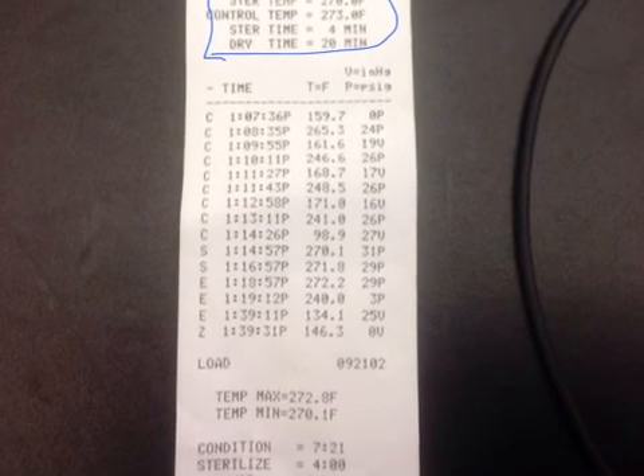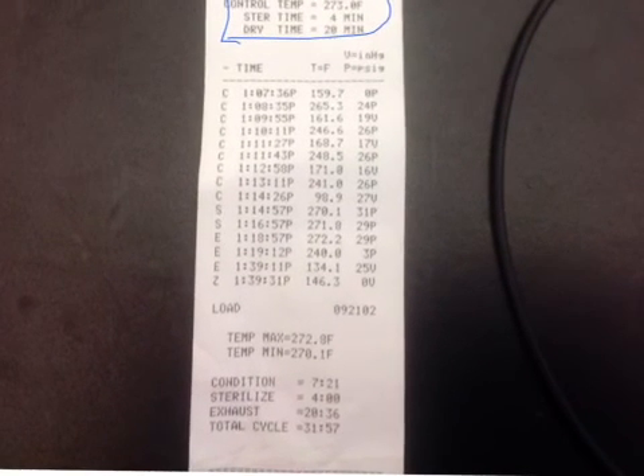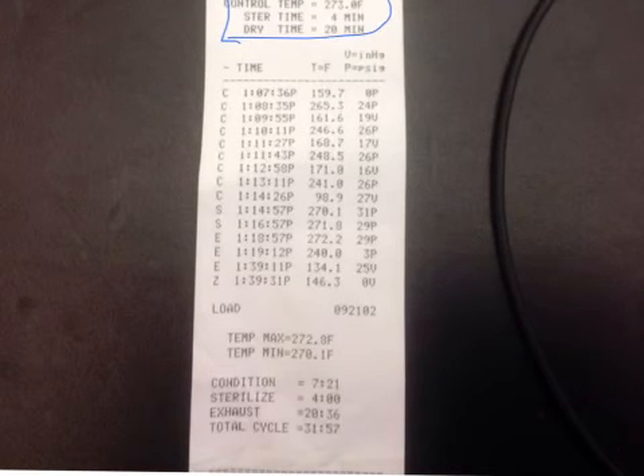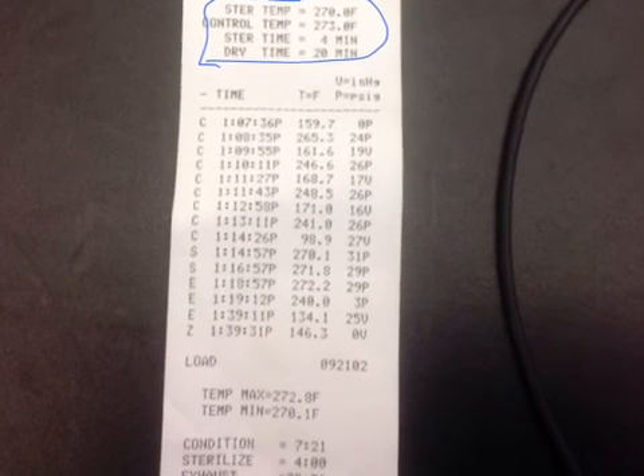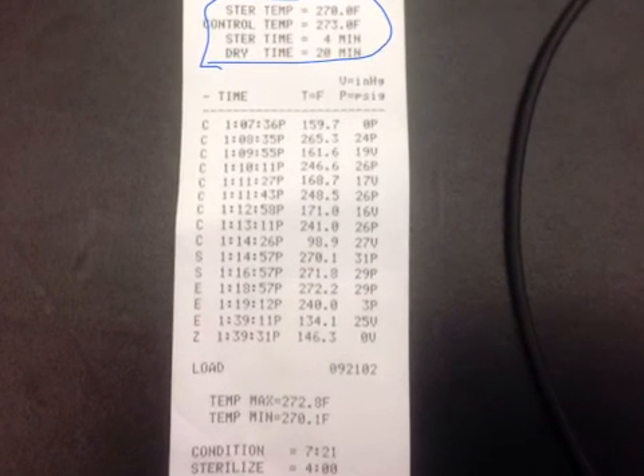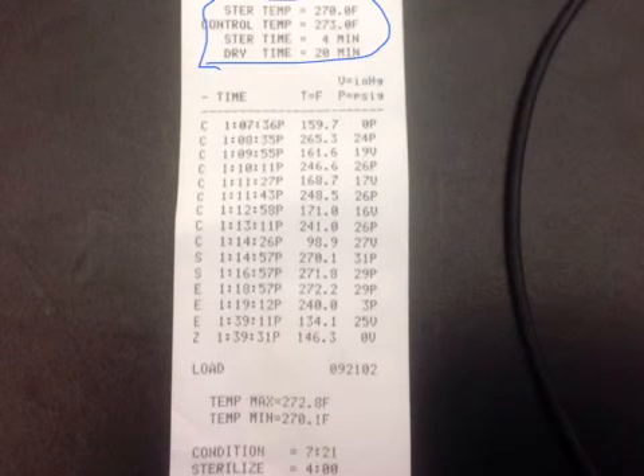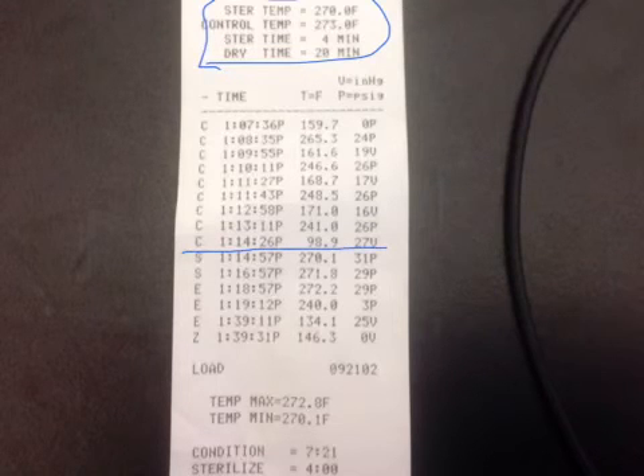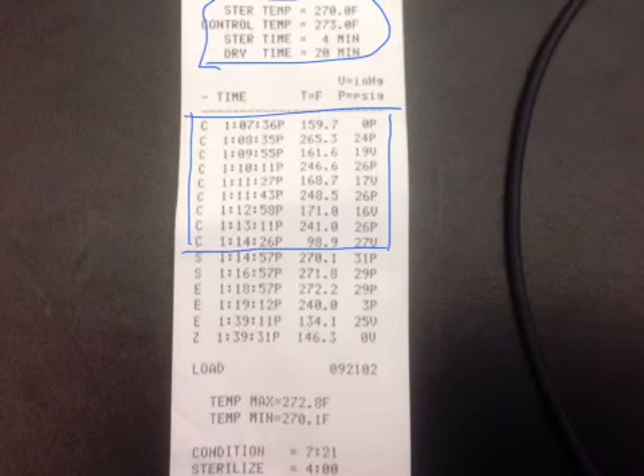And so that's going to take this total cycle. We can see down the bottom here, it took a total of 31 minutes and 57 seconds. So this is kind of an extended period of time to get 4 minutes of prevac time. In order to get that 4 minutes of prevac time, we've got to condition the chamber a good bit before we can actually get to the sterilization. All this area is part of the conditioning of the autoclave for prevac.